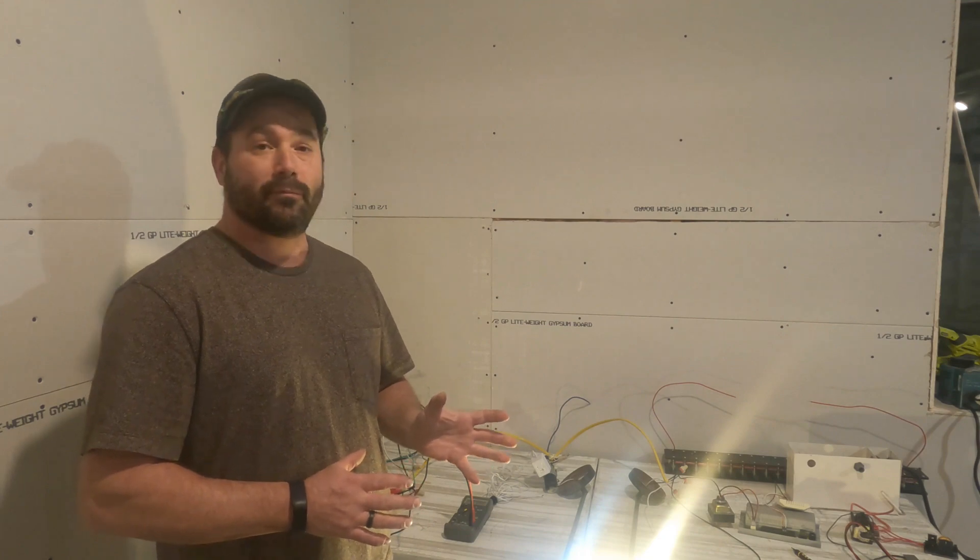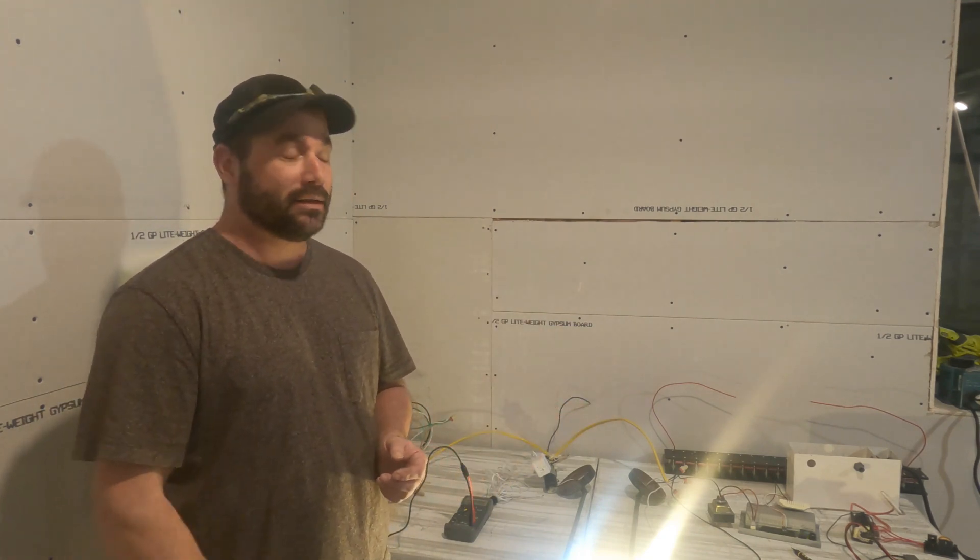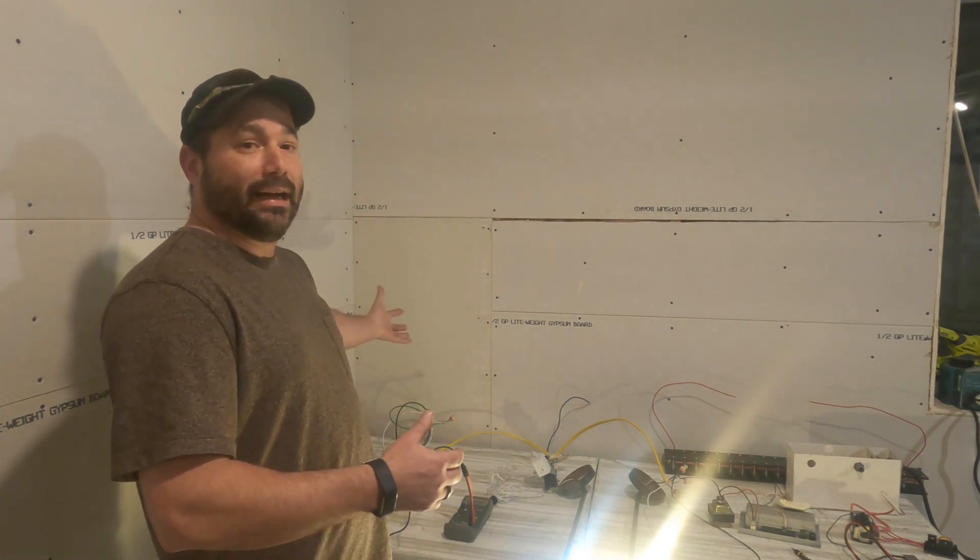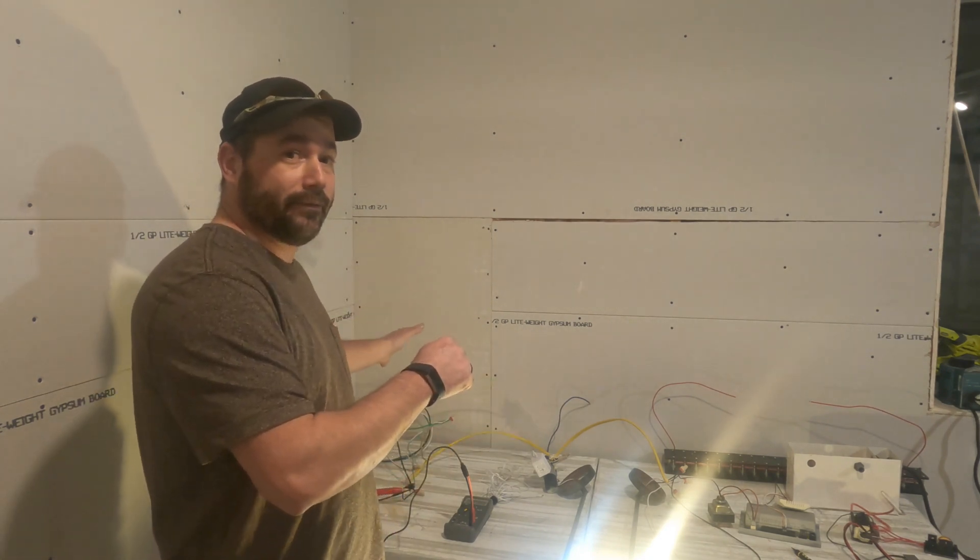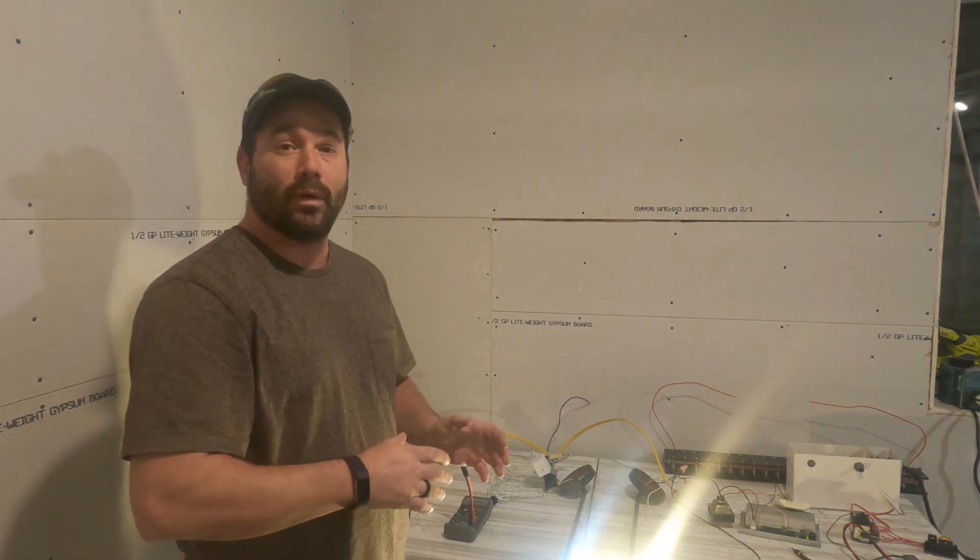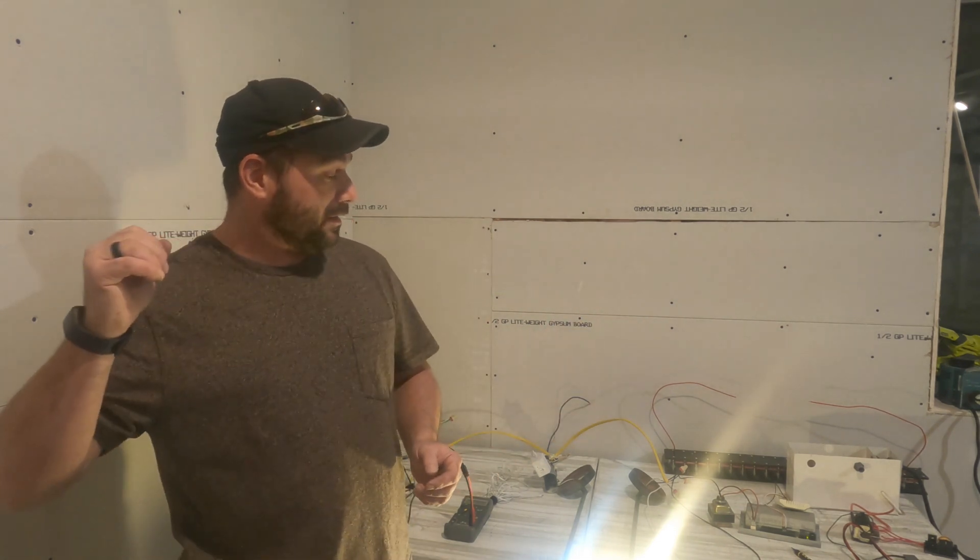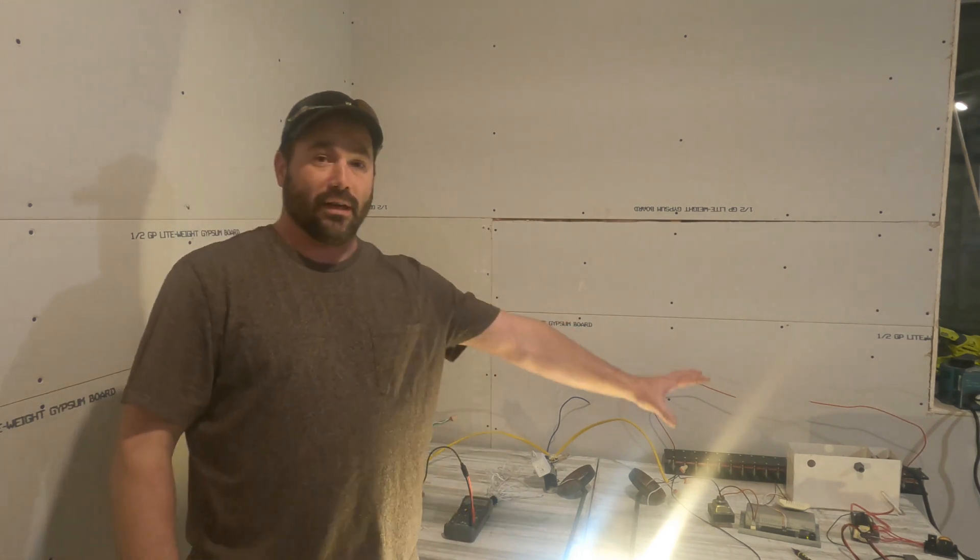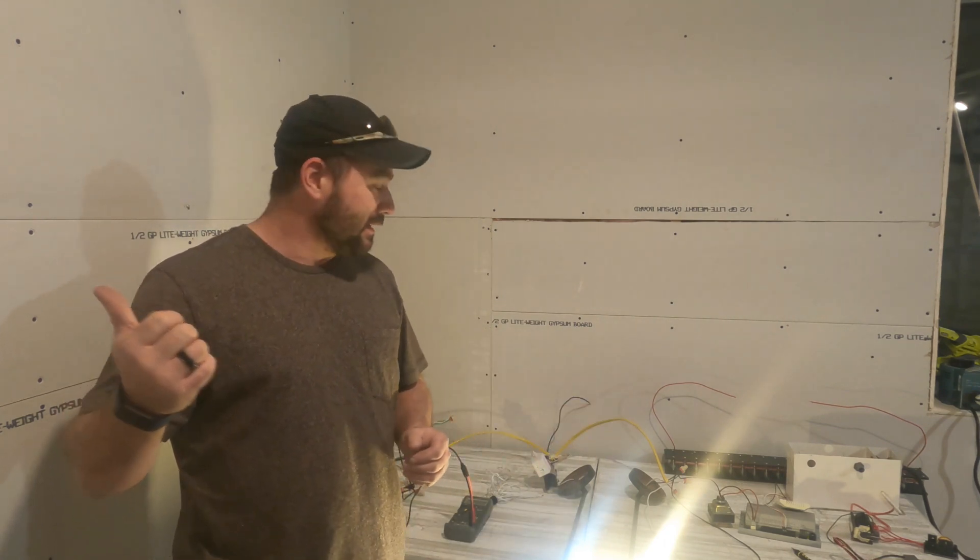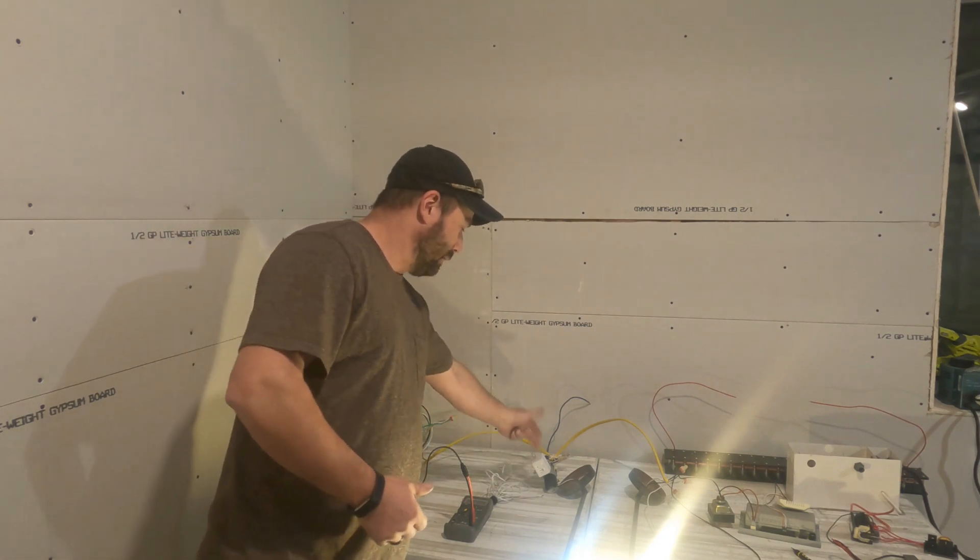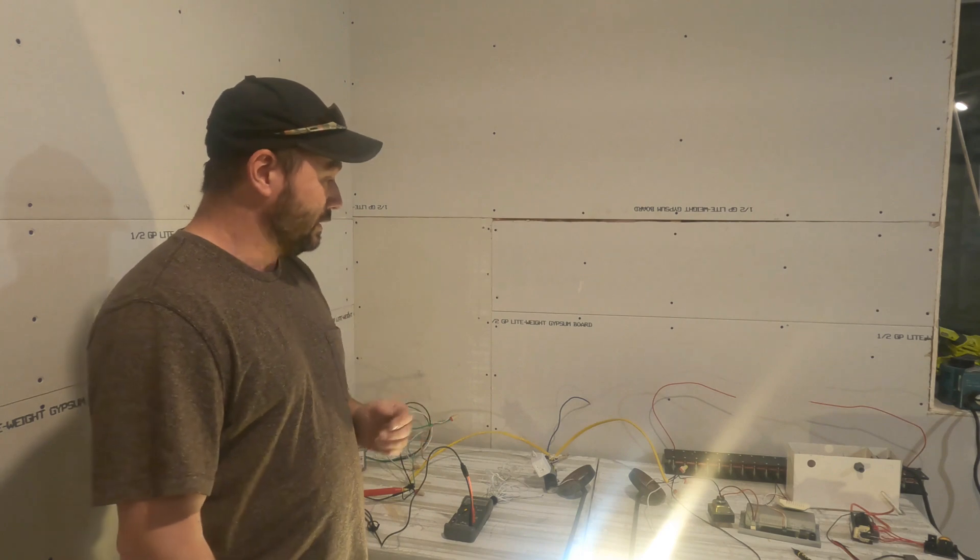This thing claims that it can protect your whole house just by being connected to your panel. So we're testing that too. So it's at the end of the line on these tests, not hitting the panel first, which would be hitting it first, shunting to ground. We're hitting at the end of the line, which would be your house side. And we're hitting all of these voltages on the house side. So it's going to be hitting the electronics on essentially your thermostat and HVAC system first, LED lights, GFCI. We've got some power pack in there. And that's essentially what we're doing.